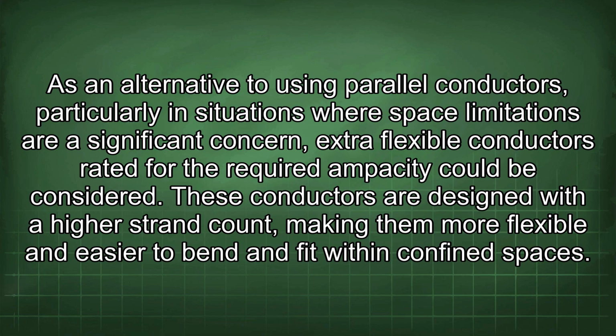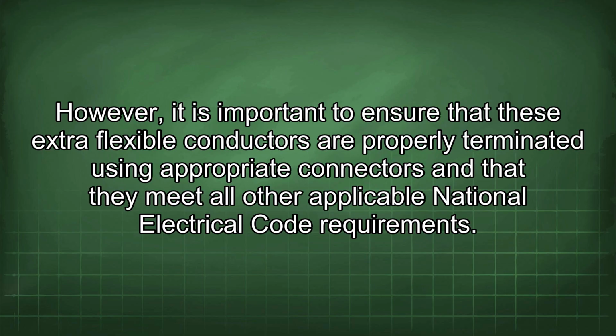As an alternative to using parallel conductors, particularly in situations where space limitations are a significant concern, extra flexible conductors rated for the required ampacity could be considered. These conductors are designed with a higher strand count, making them more flexible and easier to bend and fit within confined spaces. However, it is important to ensure that these extra flexible conductors are properly terminated using appropriate connectors and that they meet all other applicable National Electrical Code requirements.